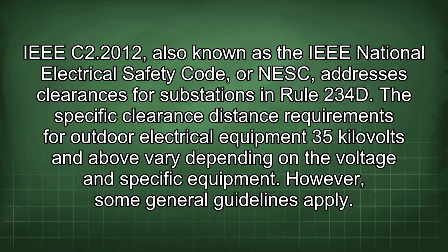IEEE C2-2012, also known as the IEEE National Electrical Safety Code, or NESC, addresses clearances for substations in Rule 234D. The specific clearance distance requirements for outdoor electrical equipment 35 kilovolts and above vary depending on the voltage and specific equipment. However, some general guidelines apply.